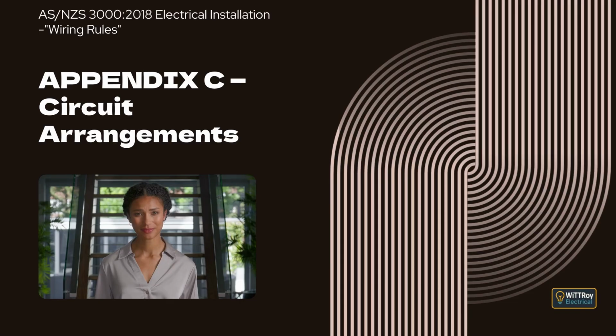Clause C 2.4.3.2, Example 6. This example explains how the alternative energy demand method is applied to an office tenancy. General lighting and power demand, along with air conditioning demand, are combined to give a total apparent power demand. This value is then converted to current using the operating voltage, providing an estimated maximum demand for the installation.